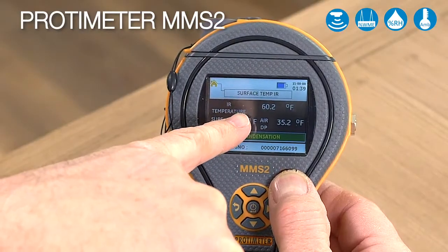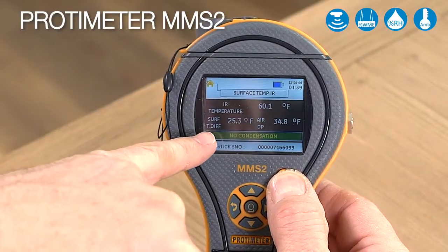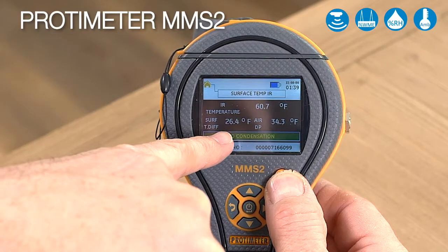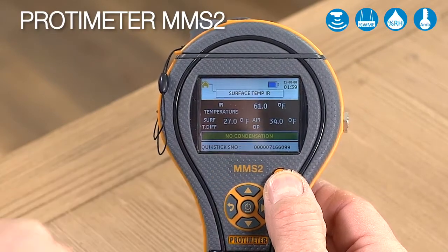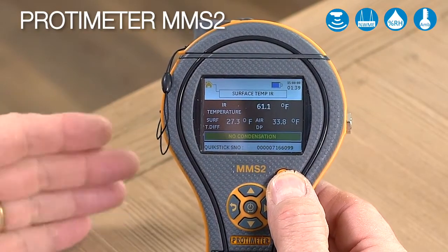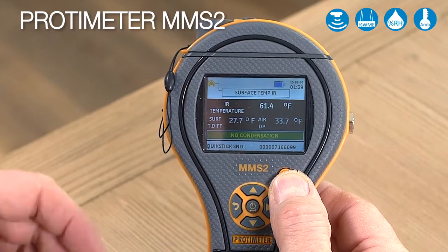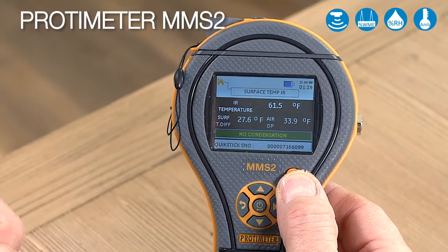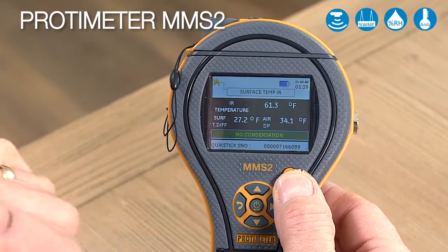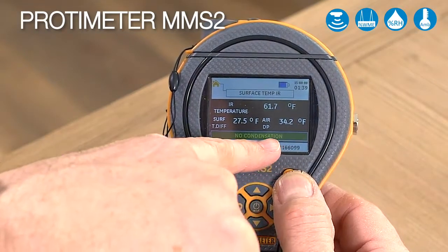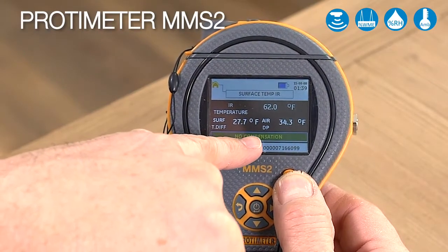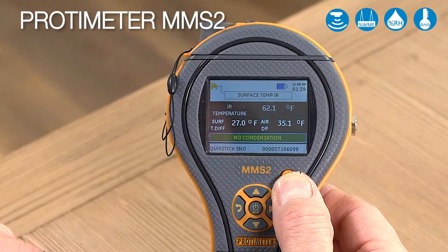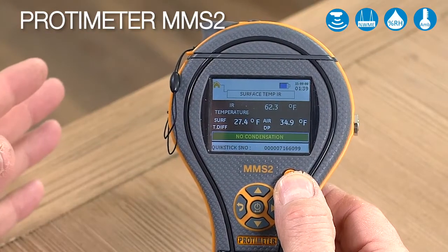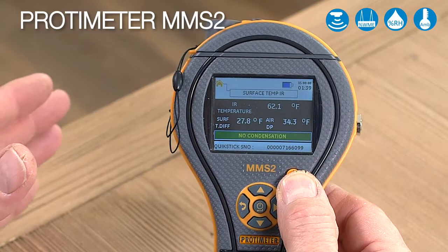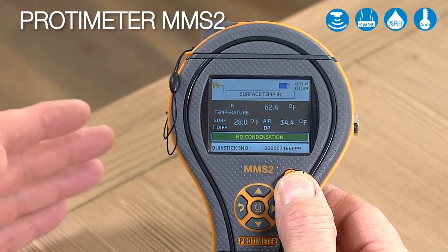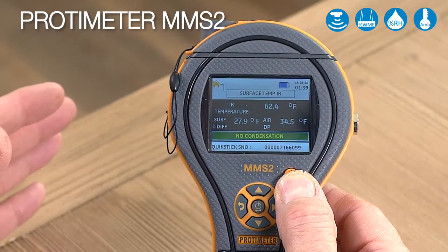On the top here it's showing the actual temperature, and then our differential to dew point. Here it's saying no condensation. You can demonstrate this easily by getting a cold drink can out of a refrigerator and pointing it at it - you'll see condensation start to form, and the lower bar will turn red to indicate condensation. This function is really useful because you often want to know whether condensation is occurring, or you're close to the point of moisture issues.